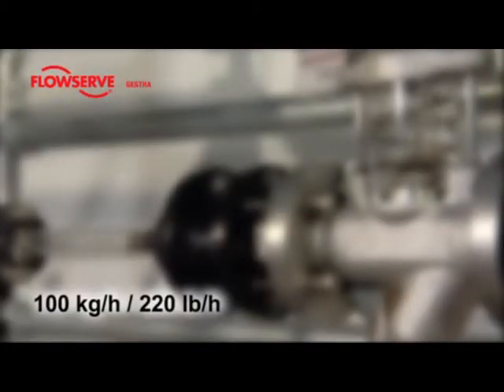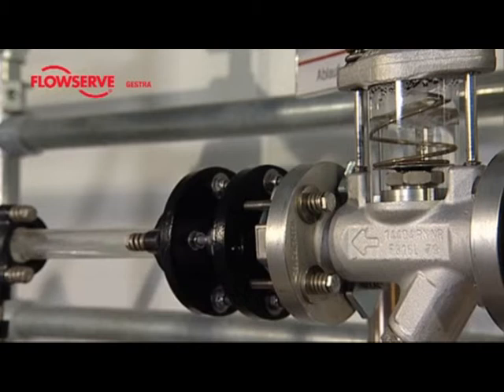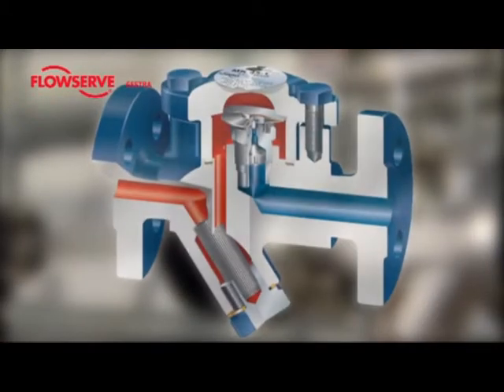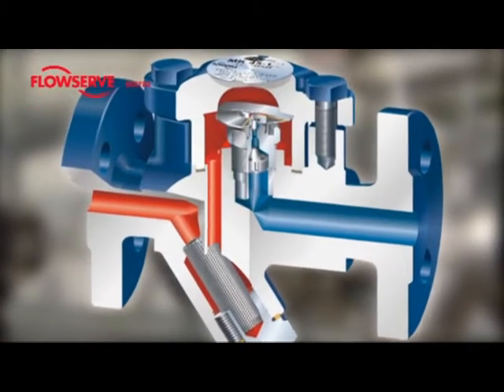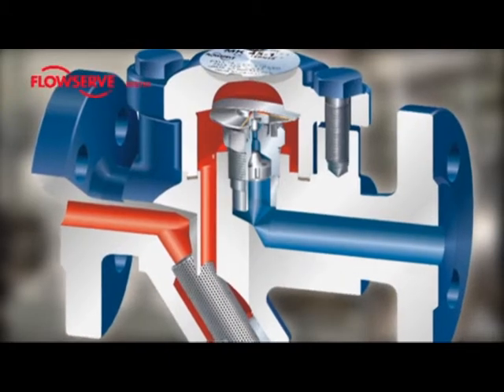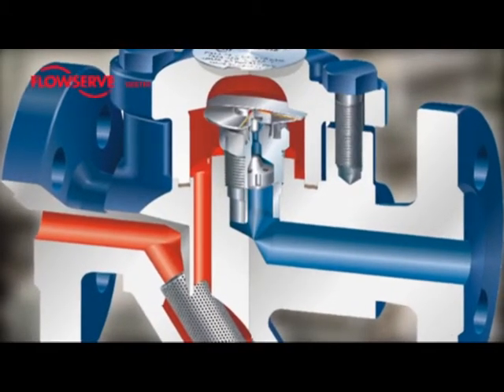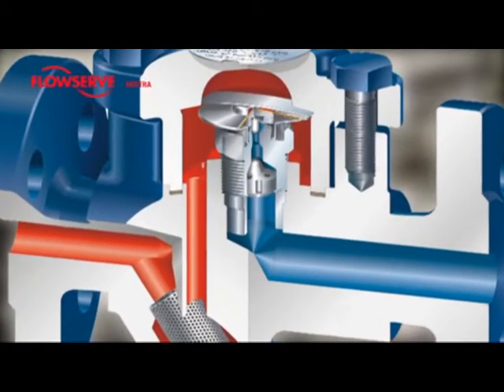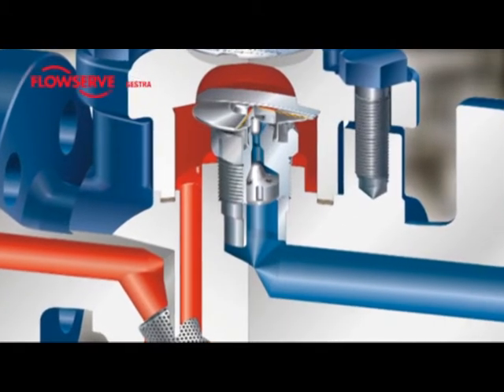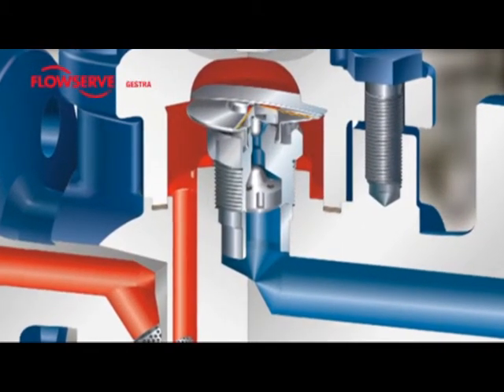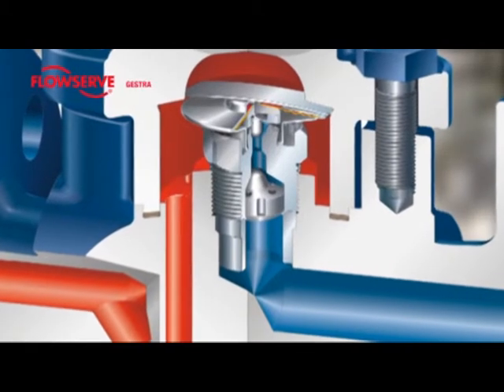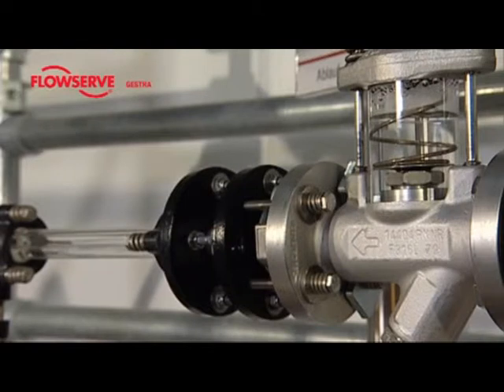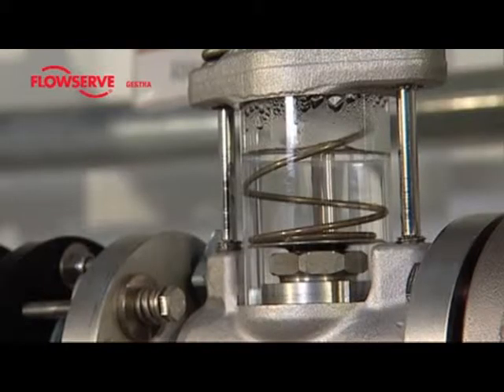If the condensate flow rate is less than 100 kilograms per hour, the Gestra tandem seat should be used. For this variant, a self-centering valve cone is integrated into the seat assembly. The valve cone has a certain freedom of movement and is able to close off the main seat before the second seat reaches the flat gasket. This provides a further guarantee of tightness, even in the presence of dirt particles. Moreover, the pressure drop over 2 stages reduces wear and extends the life of the trap.